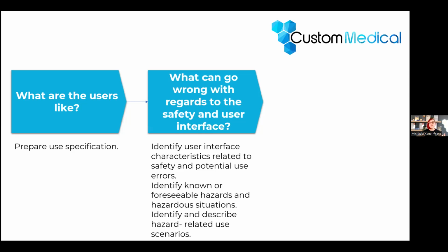If you're going for the FDA, so today is focus EU, but if you're going for the FDA also, you will have to write down some additional documents here. For instance, you will have to do a user-related risk analysis, which is one of the basic documents that you need to go to the US market.